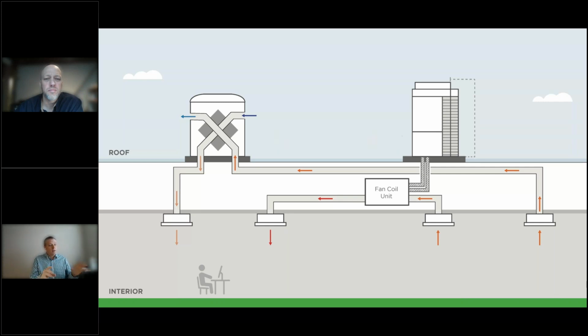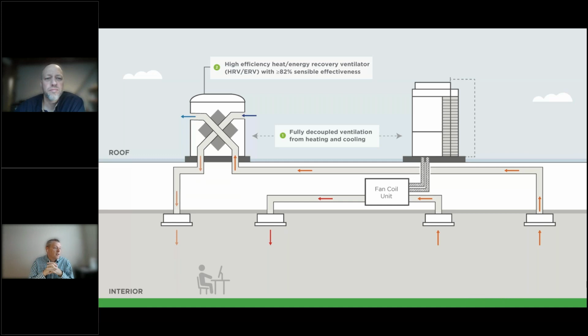The next piece of our system is the high efficiency HRV or ERV—heat recovery or energy recovery ventilators—which we require to have greater than 82% sensible effectiveness. What we're doing here is providing ventilation to the occupied space independently from the cooling. With these high efficiency ERVs and HRVs, you're preconditioning the incoming air—getting 100% outside air for ventilation, but tempering it with the return air from the space. So a lot of times you're eliminating the need for supplemental heating and cooling, because the incoming air is being preheated or pre-cooled within a few degrees of the conditioned space.